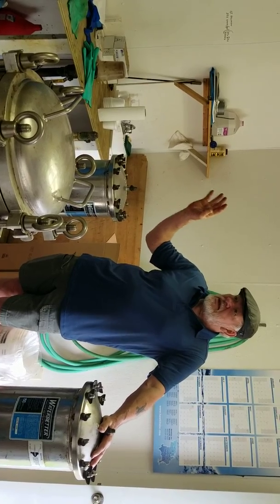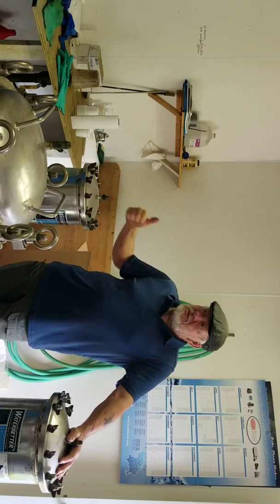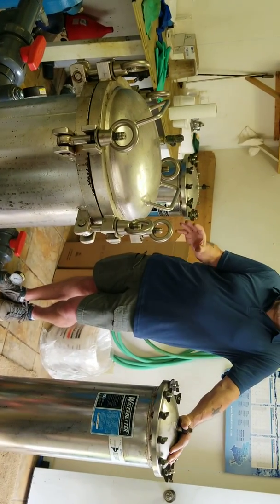So that's one of the things that we had to do when we got the system in compliance. When we first put that Tonkazorb in here, it didn't work. We still had some samples that were above the limit, and doing some bench scale experiments, we ran another sample where I let it sit with the Tonkazorb a little bit longer, and it worked fine. So by slowing the flow through the system and giving it more time to react in that contact tank, it gives us the radium reduction that we're looking for. And with that at 50 hertz, and this filter, when that starts to plug like it is getting there right now at 150 psi, that'll slow the delivery through the system down to about 15 gallons a minute. Normally it'll run about 20 to 25 gallons.